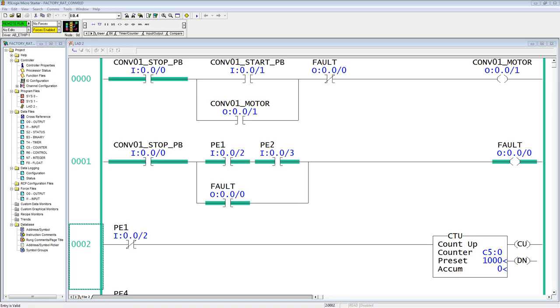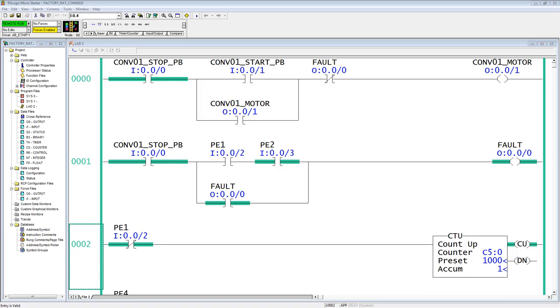Keep in mind that we're using a seal in contact because it is always possible that one of these can come unblocked due to coast of the conveyor, so we want to seal it in. At that point, the conveyor stops. You can see up above and then the operator has to come and see why it faulted, sees the carton's too large, and then once they've removed the carton, then they can push the conveyor stop button because remember the conveyor is not running and that clears the fault.